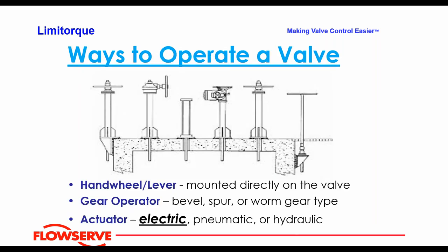Historically there are really three ways to operate a valve: a manual valve with a handwheel or lever; adding a gear operator, which gives mechanical efficiency — typically bevel, spur, or worm gear depending on whether it's multi-turn like a gate valve or quarter-turn like a butterfly valve; and an actuator. Most actuators in municipal plants are electric, though you occasionally see pneumatic and hydraulic. We're going to concentrate on electric actuators since that's the most prevalent type being installed in municipal plants.